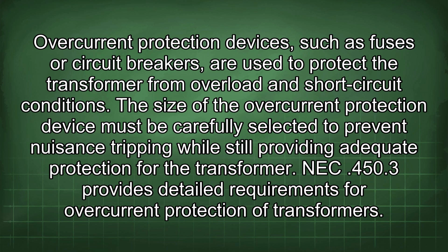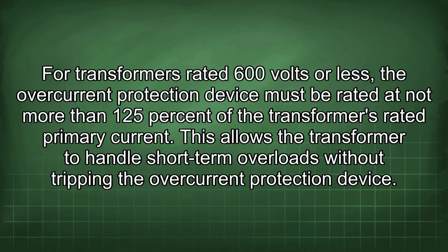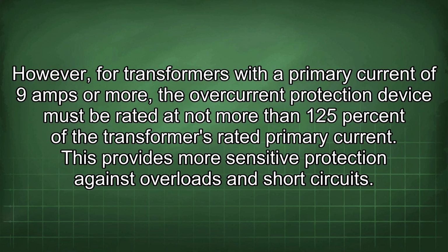NEC 450.3 provides detailed requirements for overcurrent protection of transformers. For transformers rated 600 volts or less, the overcurrent protection device must be rated at not more than 125% of the transformer's rated primary current. This allows the transformer to handle short-term overloads without tripping the overcurrent protection device. However, for transformers with a primary current of 9 amps or more, the overcurrent protection device must be rated at not more than 125% of the transformer's rated primary current.